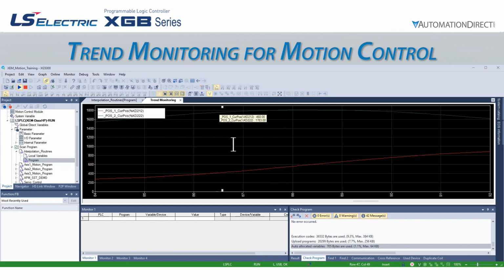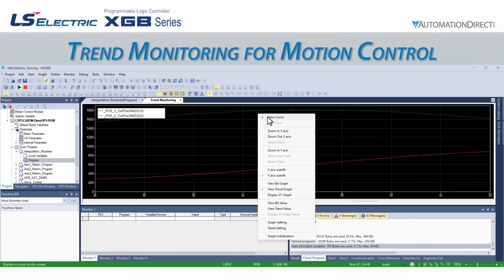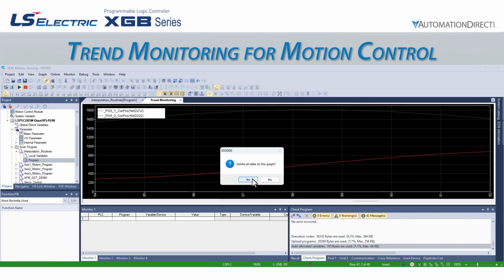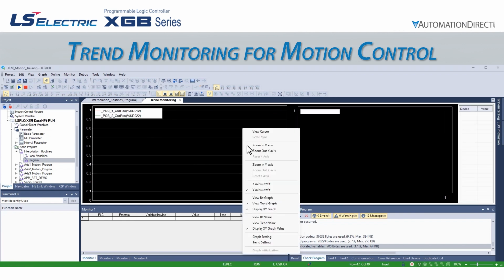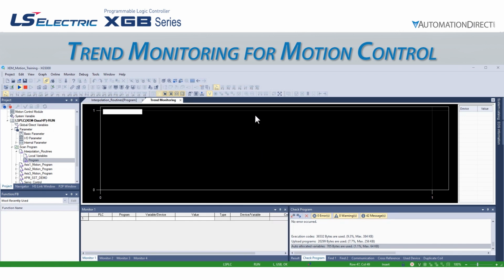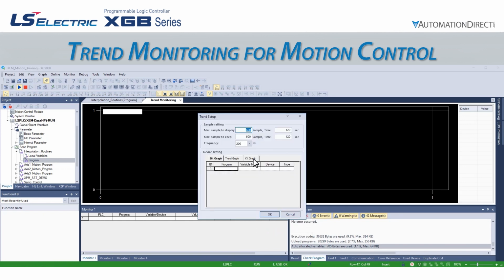The trend graph shows us each value versus time, but often we wish to see the actual pattern made by the changing values. We can use the XY graph to display the axis 1 value versus the axis 2 value. Let's reset the trend monitoring, and then right-click and select the XY graph and unselect the trend graph. We can add variables to the XY graph the same way we did with the trend graph. However, this time we'll go to the XY graph tab and add the same 2 flag variables we trended previously.